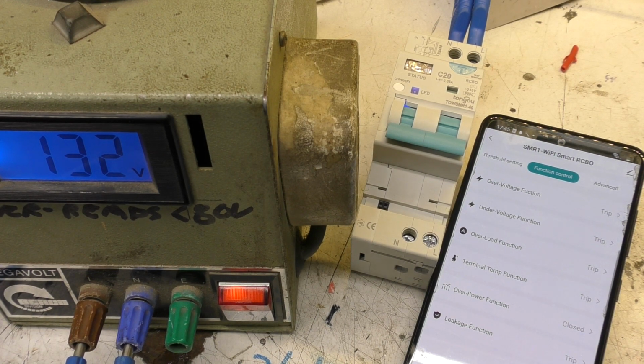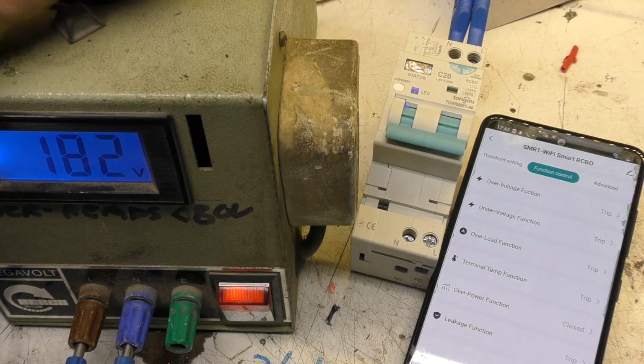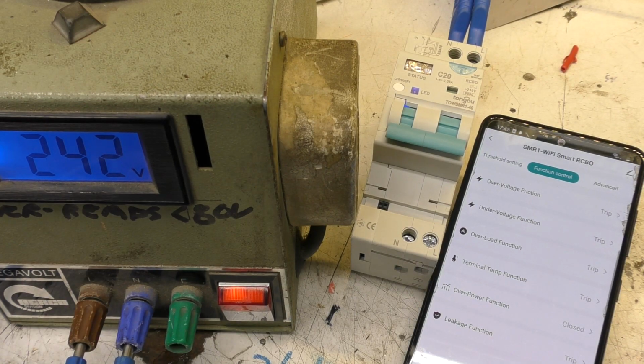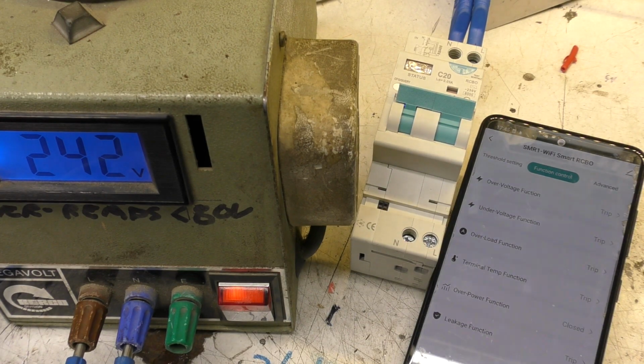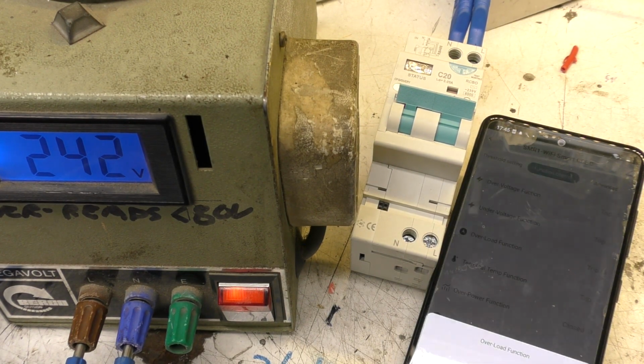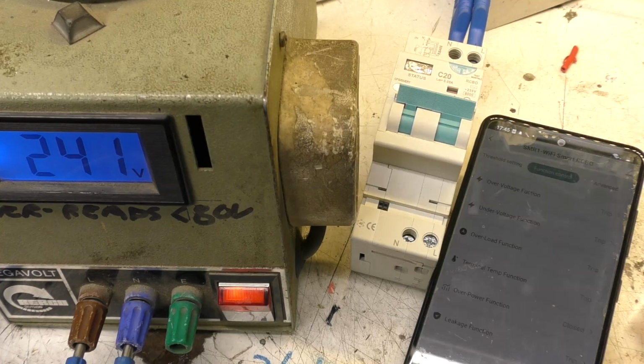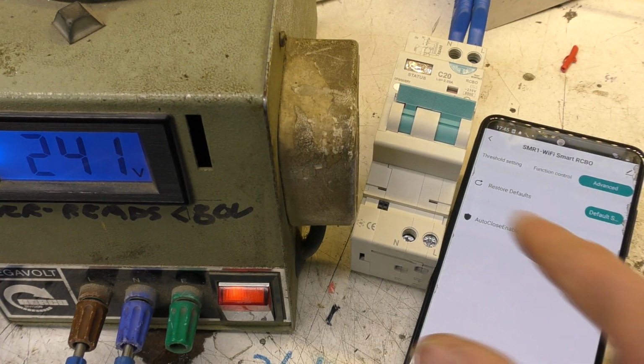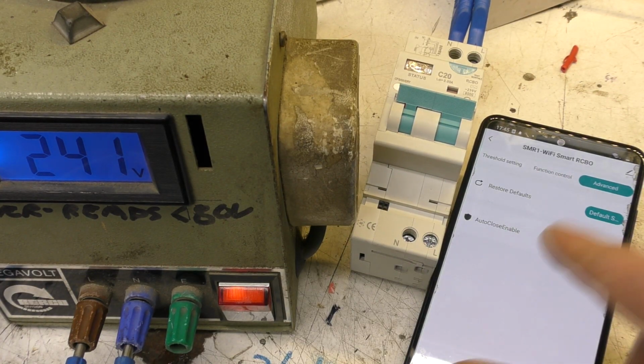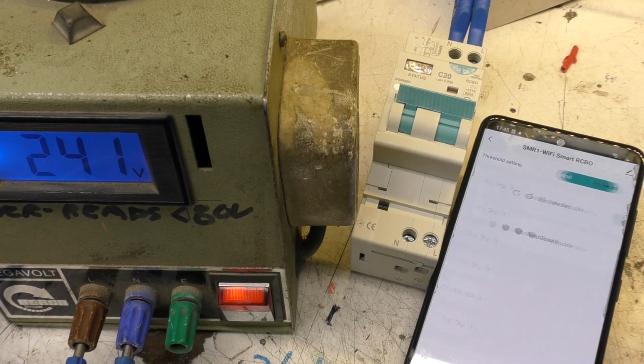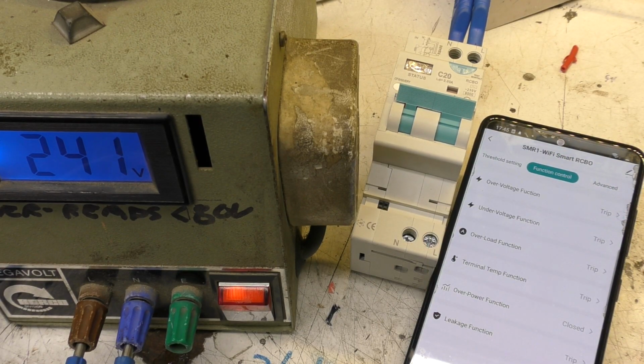But again, we have this potentially dangerous situation. You know, voltage is tripped out. You've got under voltage, something's gone wrong, someone's now trying to investigate the system. Voltage returns back to normal, then about 10 seconds later, it turns itself back on again. Wonderful. Now this is a function that you have to explicitly enable. If you go into advanced, there's auto reclose, so auto close enable, so you do have to have that enabled, but yeah, the fact you can do it is not great.